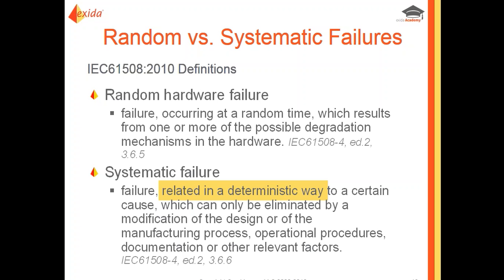The IEC systematic failure definition states: a failure related in a deterministic way to a certain cause, which can only be eliminated by a modification of the design, manufacturing process, operational procedures, documentation, or other relevant factors. That definition is better than the random one, but it's still not great, and we can absolutely understand why different sites would consider the same failure differently.